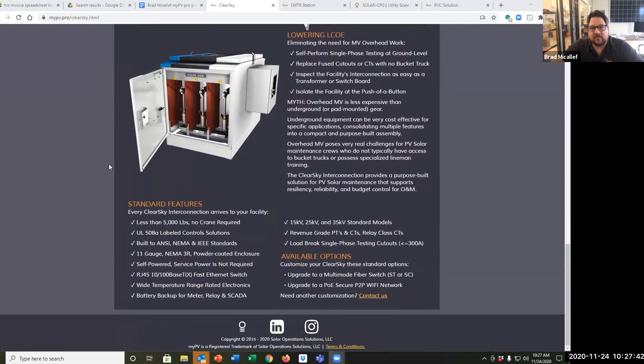You also have revenue grade metering built in, and in this version of our product we also include fused cutouts, another form of protection for your 3-phase electrical system. We provide these in a manner that supports IEEE testing requirements under 1547 for both 3-phase and single-phase drop testing, so something you'd normally need a bucket truck and specialized linemen for, you can now do from the ground. We feel this is a much safer product, and a long-term less expensive product to install, maintain, service, and operate, and it speeds up your commissioning process too.